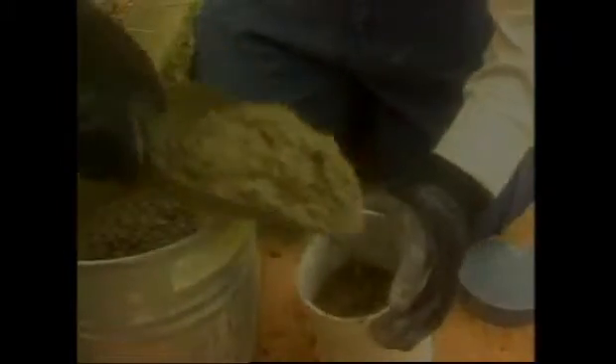Drawing on the manufacturers of concrete-based products, Geotherm's new bedding will include a selection of natural materials in varying proportions. Using locally quarried materials, Geotherm will come up with the best possible mix as a backfill so as to maximise heat dissipation. As cable laying proceeds, the replacement backfill is double-checked. Quality assurance.